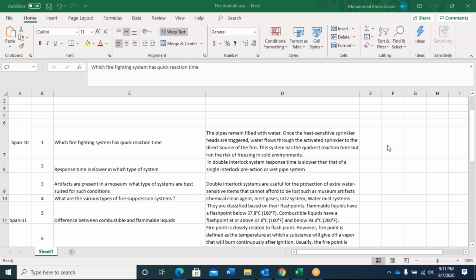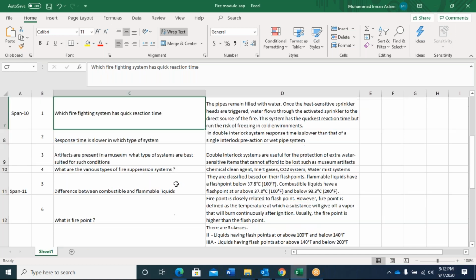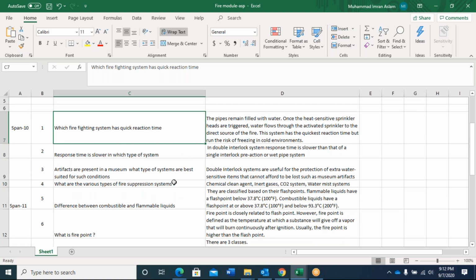We call it a wet pipe system. In a wet pipe system, the pipe remains filled with water, so once the heat sensitive sprinkler heads are triggered, water flows through the activated sprinkler directly to the source of the fire. So this system has a quick reaction time, but runs the risk of freezing in a cold environment - for example, if someone is working in a cold freezer room, this system will not work there. But the wet pipe system has a very quick response time when a fire takes place.